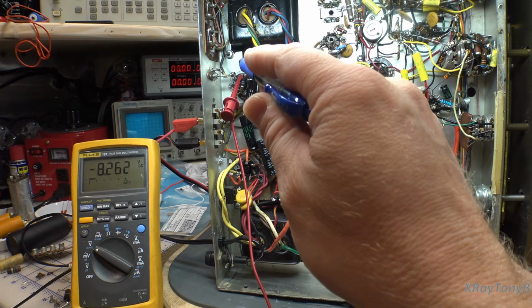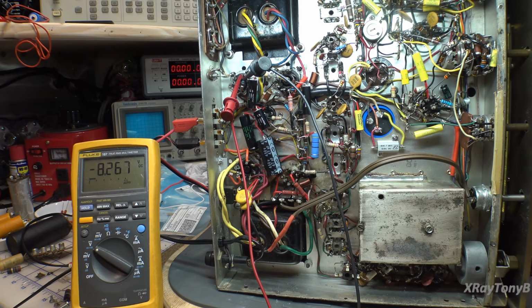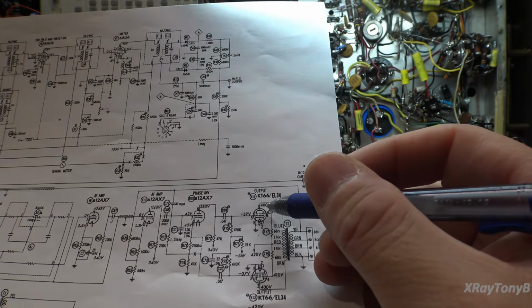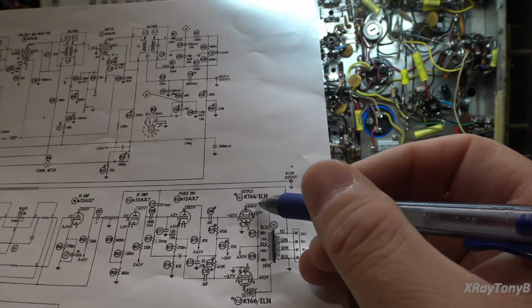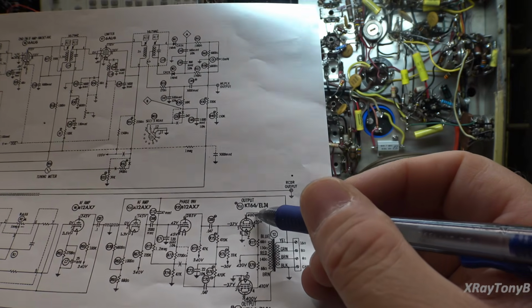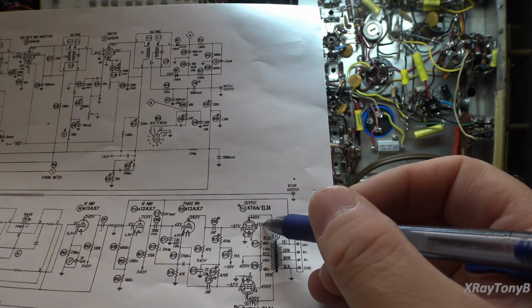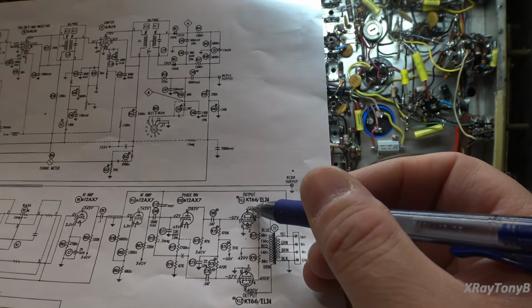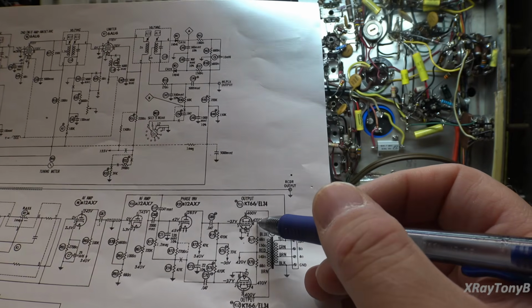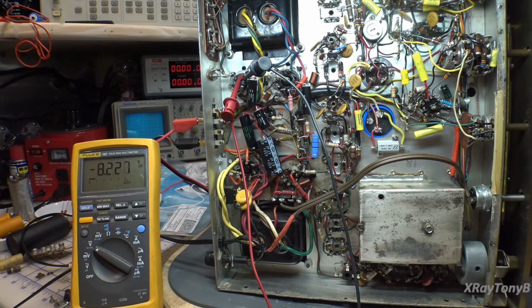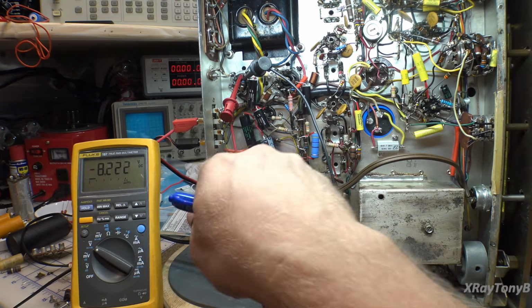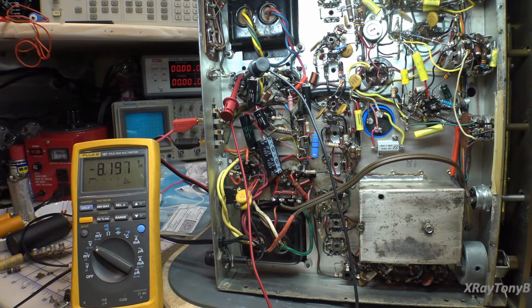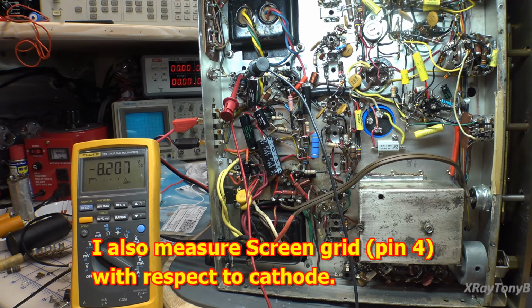I've now moved my probes onto the screen grid, which is pin 4, and to pin 3 right here. Don't pay attention to these voltages right now, that's not what we're measuring -- those are with reference to ground. We're going to measure the voltage drop between the cathode and the screen grid, and when we look at it, that voltage drop is about 8.2 volts. So we're going to write that down now.